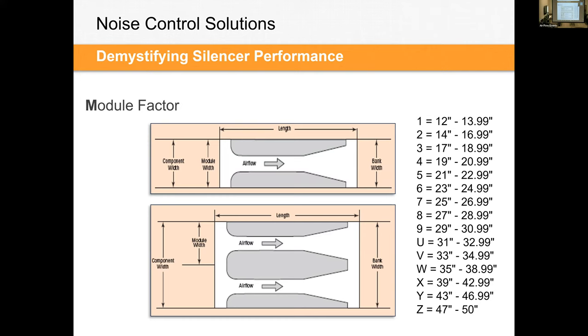And these modules have different widths. And the width range is depicted with a number or a letter. Because again, we're magicians using magic numbers and letters. We want it to be sort of sneaky for our competitors not to be able to copy our designs. So for example, a 6 module factor would be anything that falls between 23 and 24.99. So if this silencer was, say, 24 inches wide, a 6 module factor would work well in there.